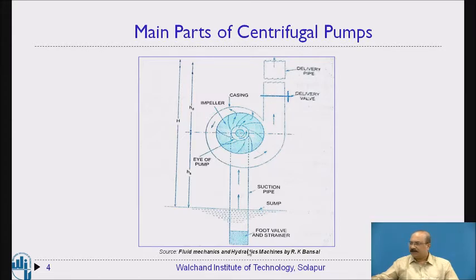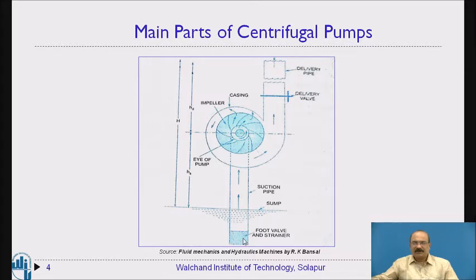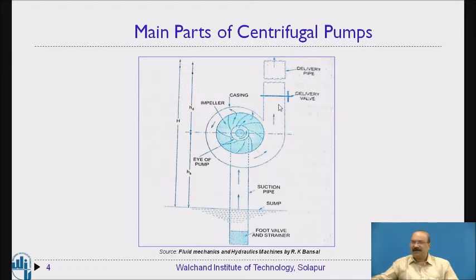The inlet takes place through this particular section, which we call the suction pipe. Here we are providing a foot valve and a strainer, because any unwanted dirt should not enter the pipe — that is the reason we provide a strainer, which also acts as a filter. This is the suction part, and then it connects to the impeller. These are the blades of the impeller, and this particular part — the inlet of the impeller — we call the eye. Then this is the delivery pipe.